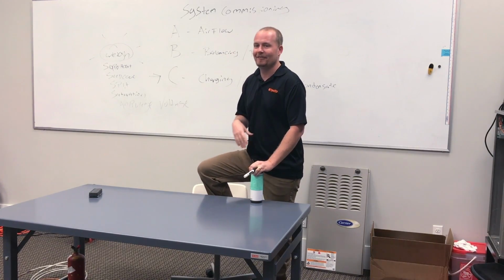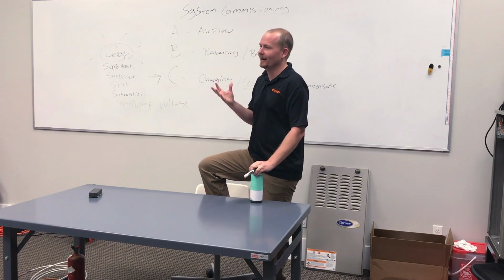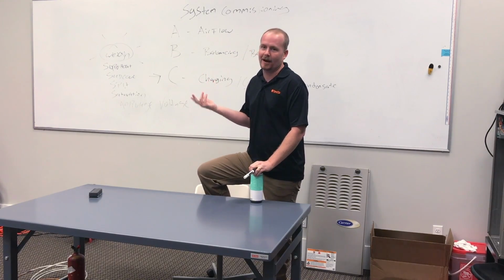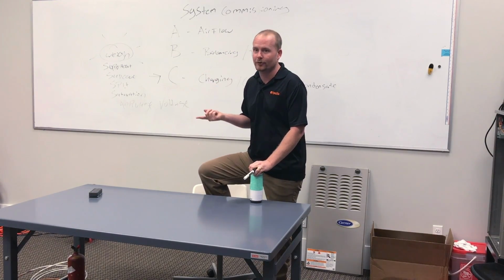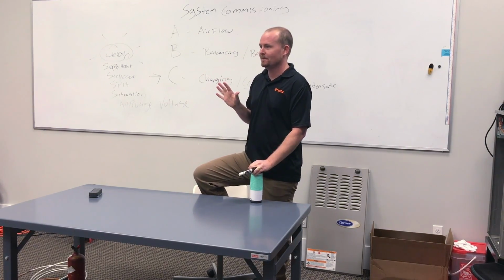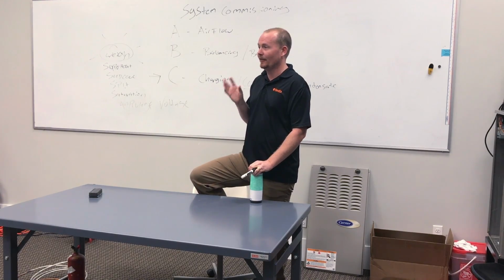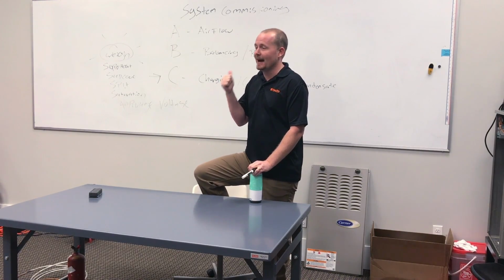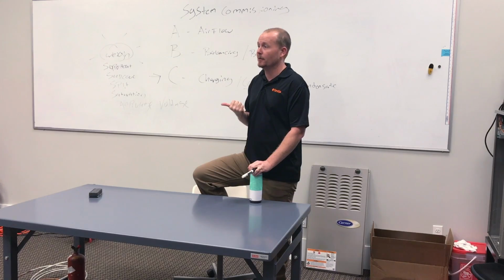I don't care. If we've got to go back the next day, I don't care. If you've got to wake me up in the middle of the night and I'll open up the office to get you a vacuum pump, that's what we do, if that's the only option. You understand me? We get a vacuum pump. That's how that works. You keep clean vacuum pump oil in your pump, that's going to make your pump last a lot longer.